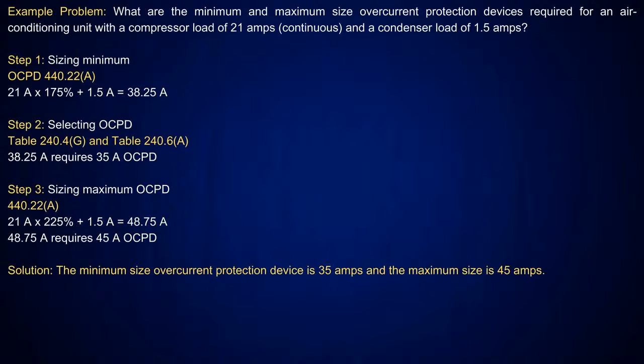Well, where did they get that minimum maximum setting from? There had to be a percentage they had to go by. Well, they went by the code because it's designed that way. Okay. Sure. And that's one of the things: when UL is going out and they're listing and labeling equipment, they're going to look at the equipment and take the NEC into consideration. So if you have a UL listing, say for EVSE, and they tell you don't put GFCI on it, guess what? The NEC was taken into consideration.